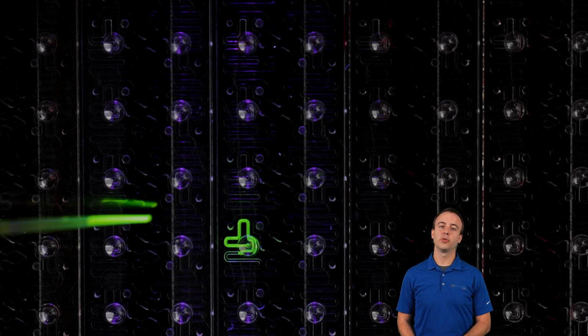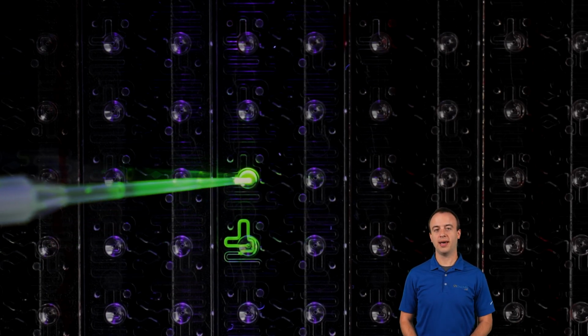We'll start off by loading our Stunner plate. Just pipette in 2 microliters of sample, and the microfluidic channels pull your samples in. Once your sample is going to be read, it gets pulled through 2 microcuvettes with fixed path lengths to ensure the most accurate and precise UV vis concentration data and light scattering data from the smallest possible volume.